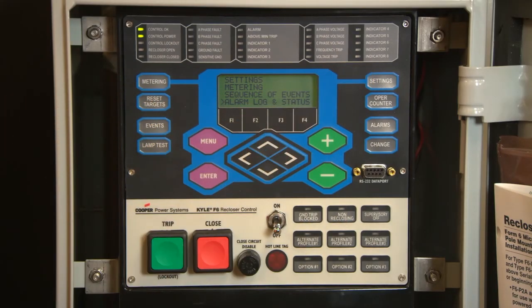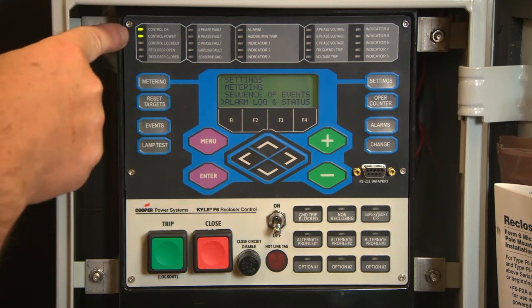It will be interfaced with a WVE recloser. Let's take a look at the top row of indicators. If the AC supply is active and the control has performed a self-diagnostic, the control OK and control power indicators will both be green. Should the control go to a lockout state after a trip, the control lockout indicator will turn red. The recloser will be open at this point, causing the recloser open indicator to also turn red. The recloser closed indicator will turn red when the recloser is in a closed position.